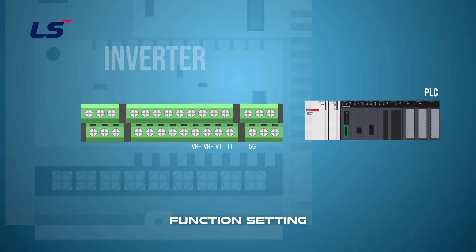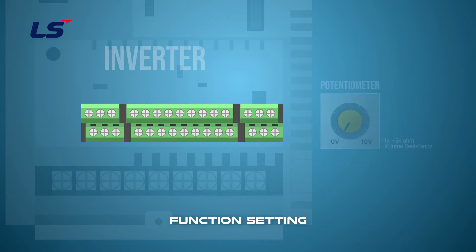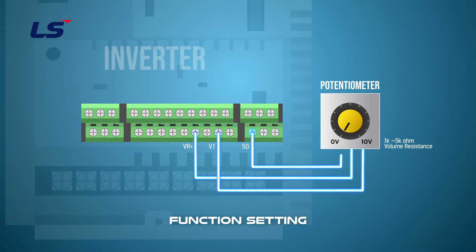When entering output voltage of external device, you wire the V1 and 5G terminals, or I1 and 5G terminals properly, to drive's terminals as mentioned above. When using drive's internal power source, you can wire a potentiometer of 1K to 5K ohm to VR plus, V1, and 5G.